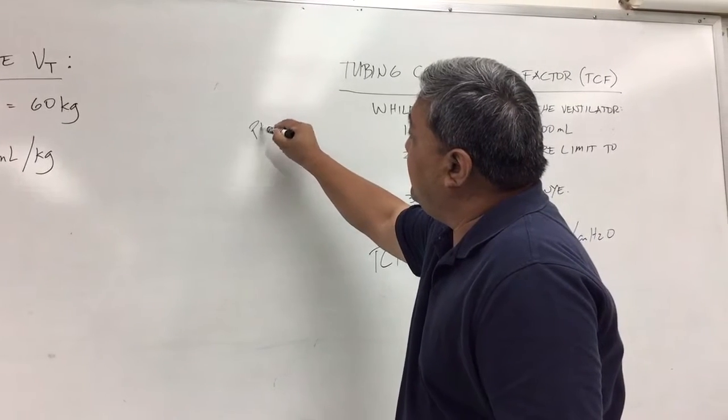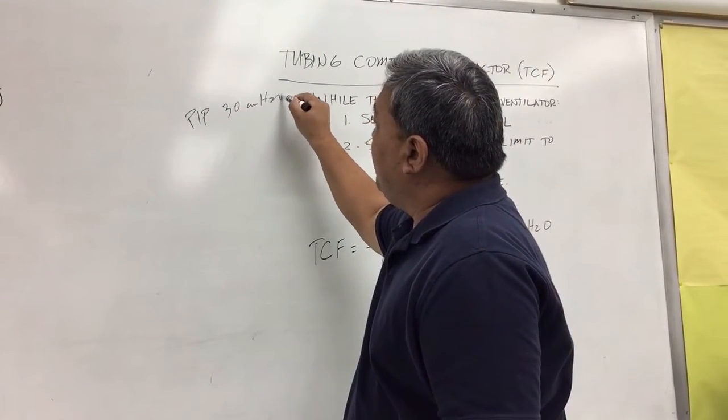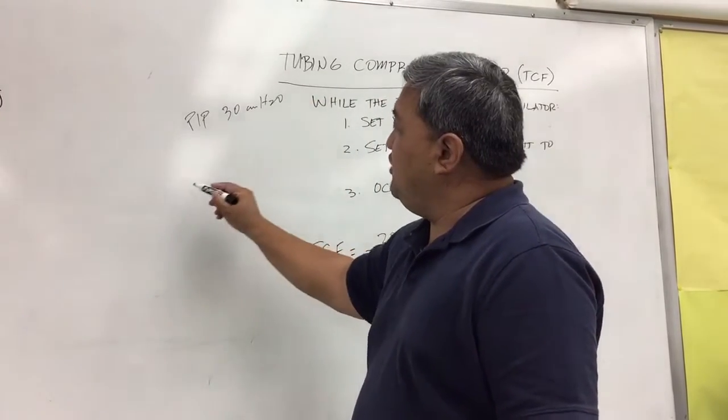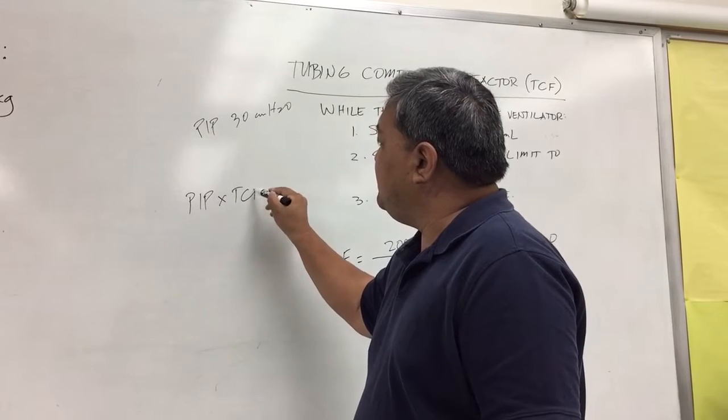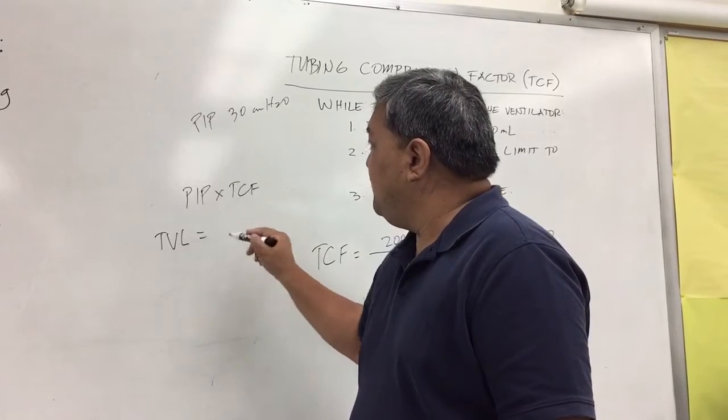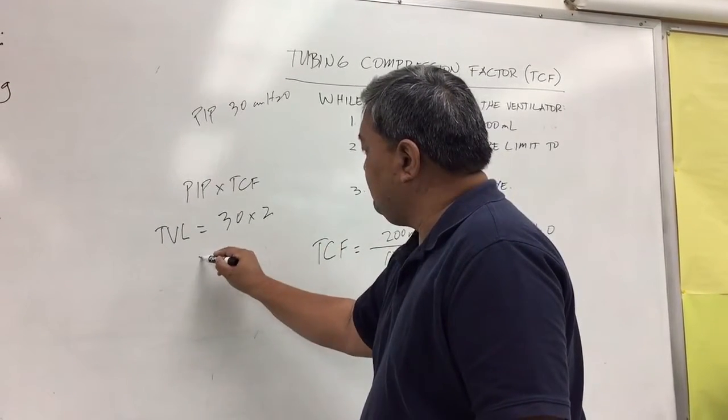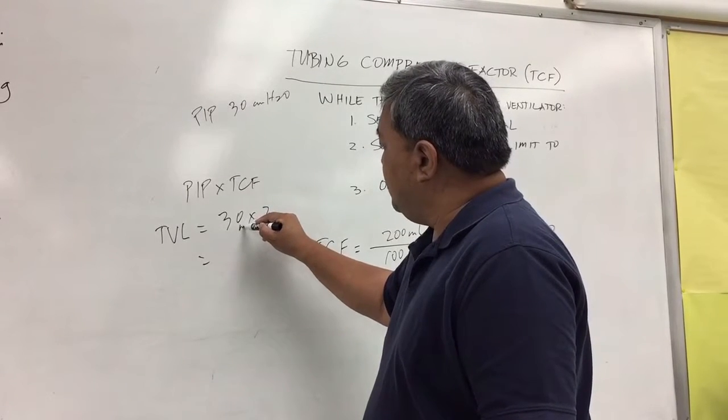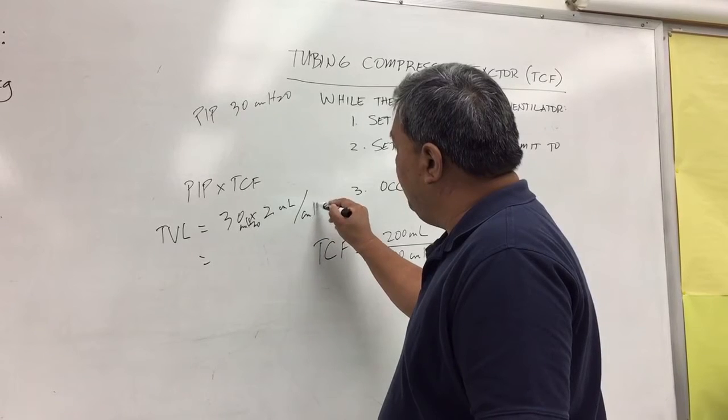While the patient is on the ventilator, let's say it delivers a PIP of 30 centimeters of water pressure. What you're going to do now is multiply the PIP by the TCF to get the tubing volume lost. So 30 times 2 - this is your centimeters of water pressure times mls per centimeter of water pressure.